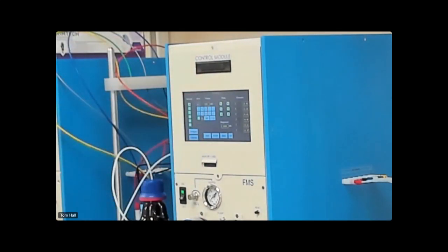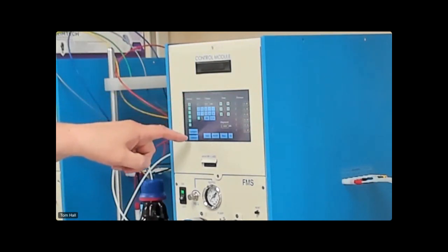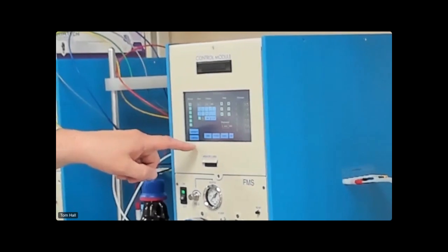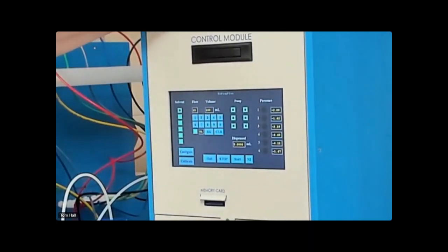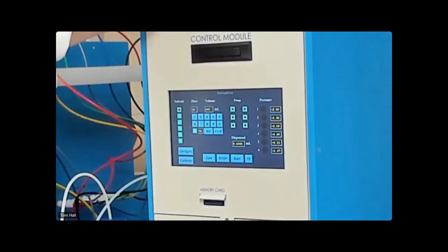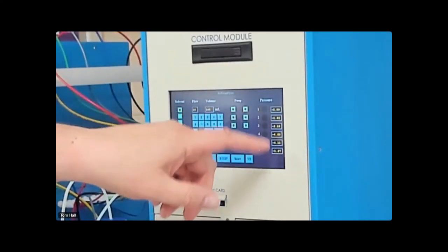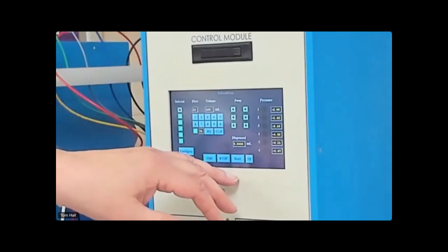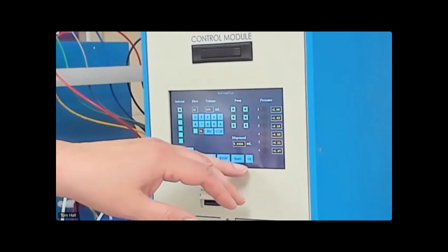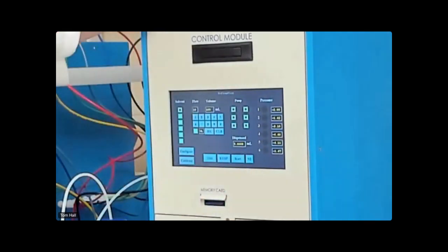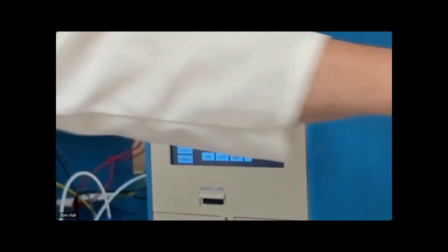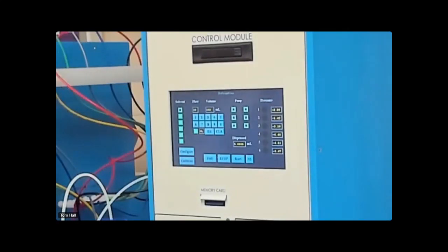Here we have the layout. You can choose up to 6 solvents here. There's a calibration function also. Here you set the flow and the volume. Those are the 2 most important parts. You can select each of the 6 pumps, so if you just want to run a few samples, not 6, you can do that. Here you have a real-time pressure readout, which will be activated once you start the flow through the columns. Here we have the nitrogen key that you can use to blow out the solvents or the sample reservoirs here. We call them sample reservoirs, or syringe vials, they're also called.